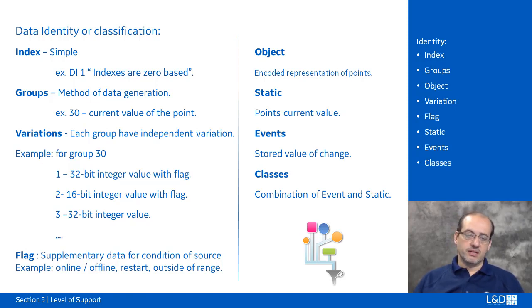Digital input 2 would refer to another status, maybe of the same breaker or a different breaker. But what we end up with is a grid of information that basically points out an index to every piece of data or information coming from the field. It is built into this grid of information that is transmitted from the primary devices in the field to the secondary devices in the field, all the way until it reaches the control centers as information transmitted over DNP.